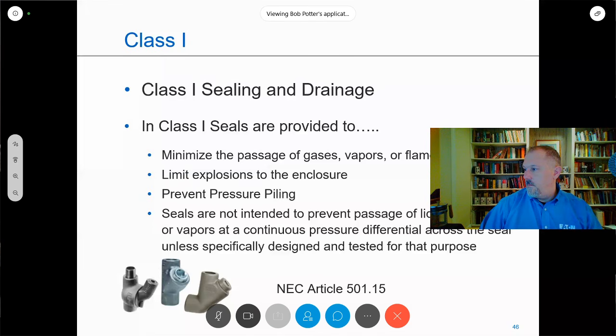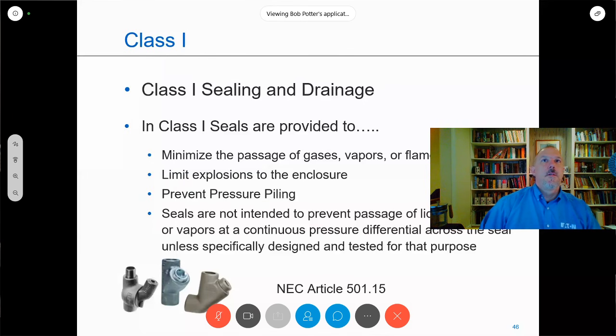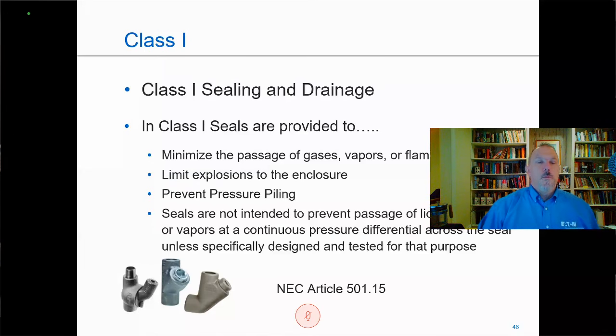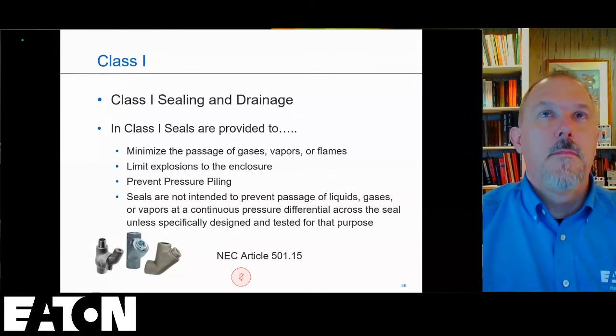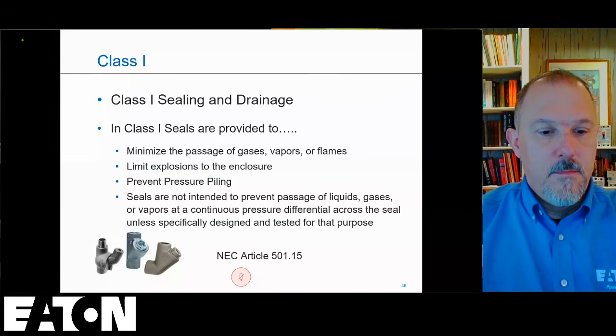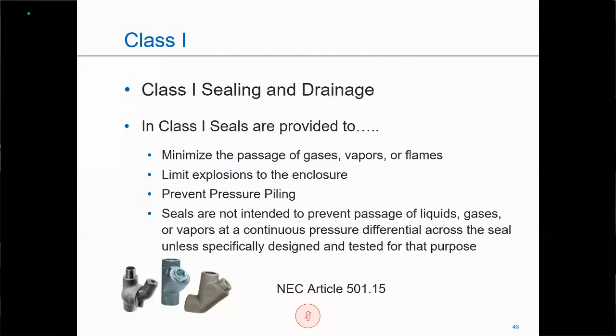So sealing fittings, probably one of the most important yet misused, abused and misunderstood items in all of hazardous location areas. Sealing fittings are designed to minimize the passage of gases, vapors, or flames from traveling through my conduit system. It's going to limit the explosion to the enclosure. So that enclosure will do what it was designed to do: contain the explosion, cool the gases, and harmlessly release those back out to the atmosphere. And it's going to prevent pressure piling.